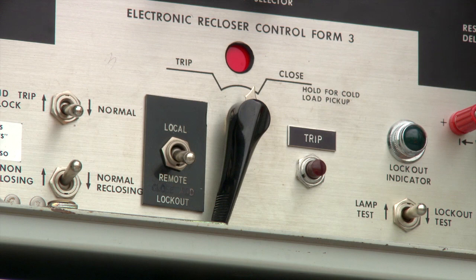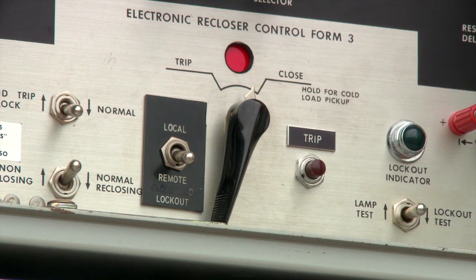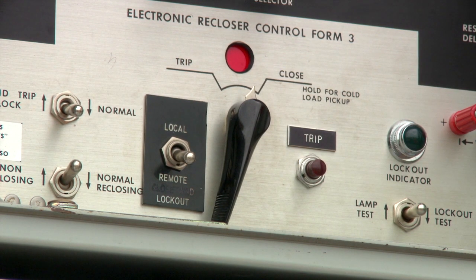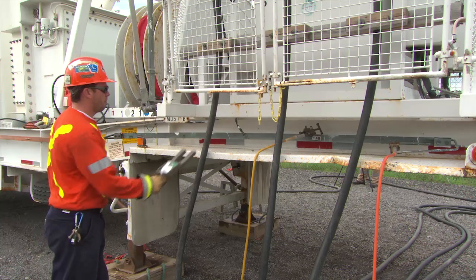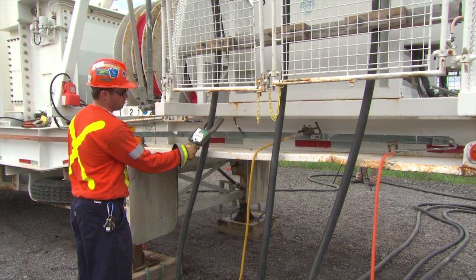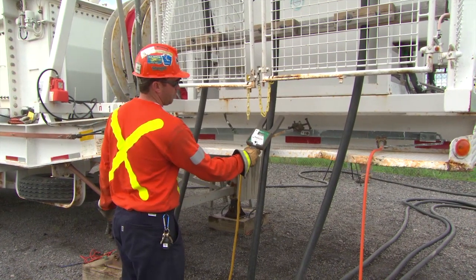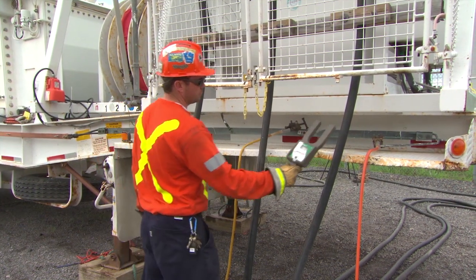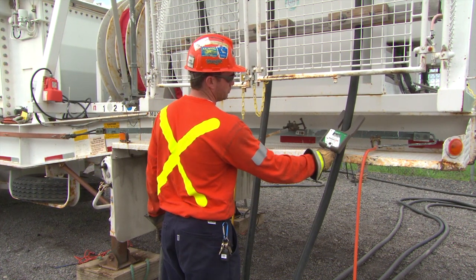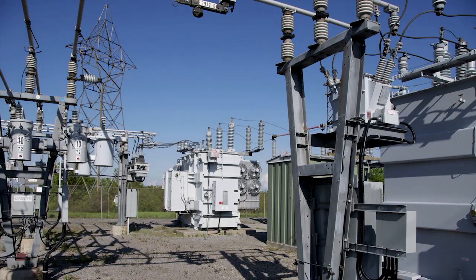If the single-phase load to be switched in is greater than the MUS feeder ground trip resistor amperage, then block the MUS feeder ground trip feature until after the single-phase switching has been completed. Check current on all cables using the amp stick sensor link horseshoe CT. The MUS and DS are now in parallel.